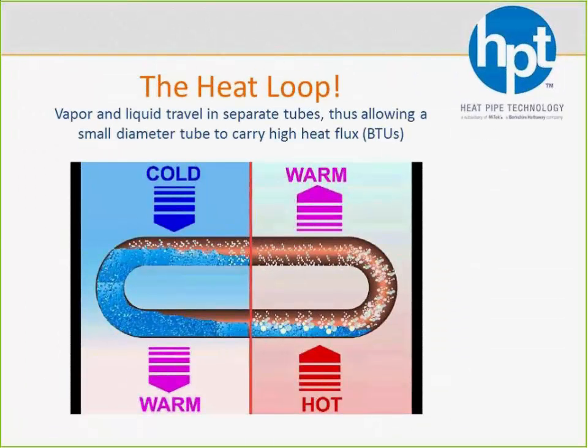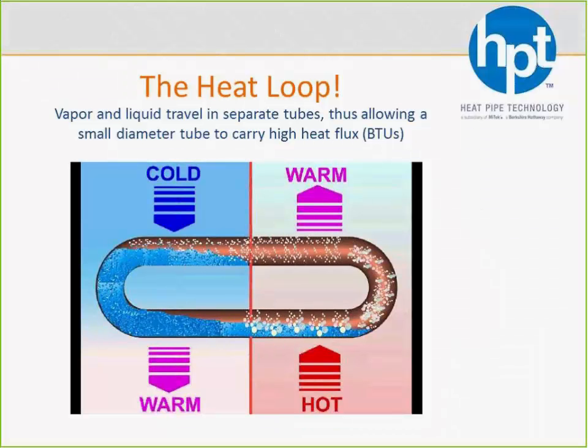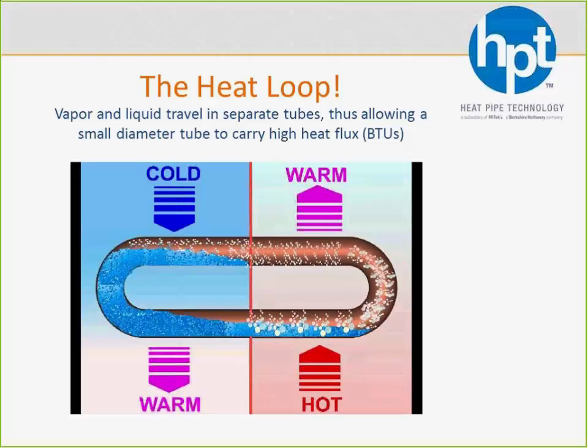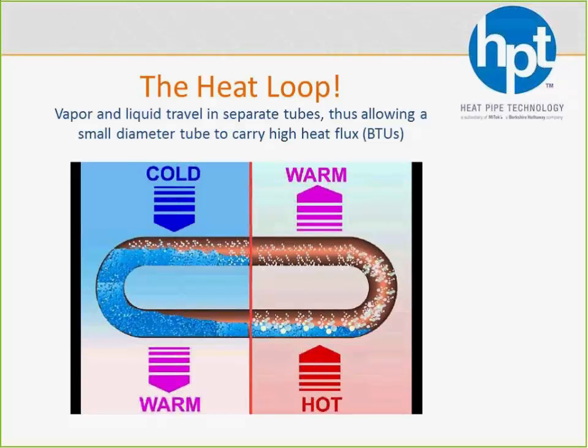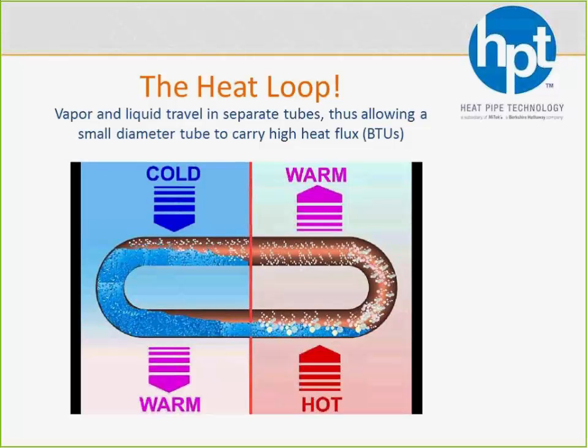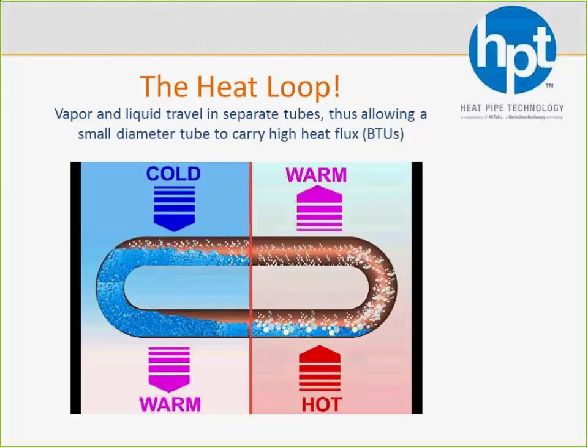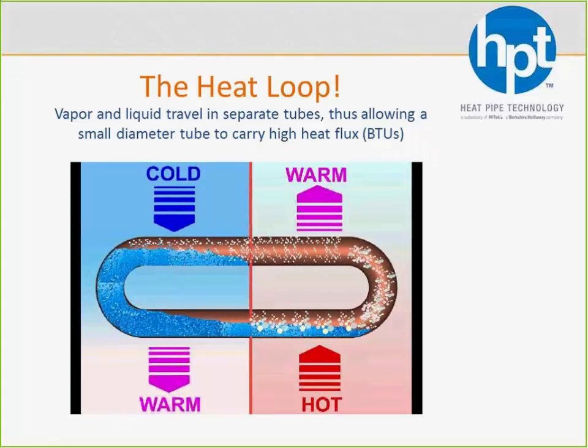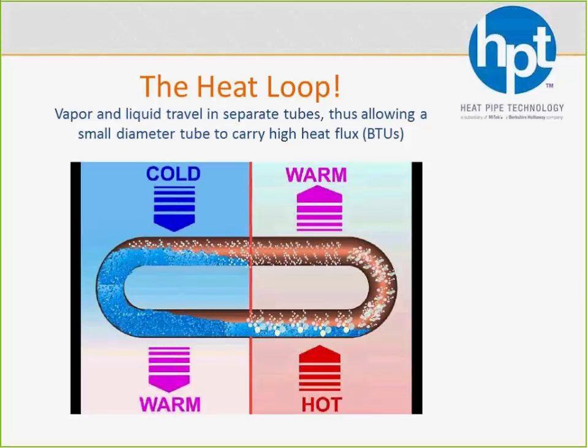We do it a little bit differently. We use what we call a loop circuit, where instead of a single tube with the heat going back and forth, we actually have what kind of looks like a racetrack, where you're going to have the liquid going one way, and let's say we're going from left to right here. The liquid's going to enter that hot air stream. It's going to pick up that heat and boil. It's actually going to go up the loop and then loop to the other side, where it contacts the cooler air stream, gives off the heat, condenses back to a liquid, goes down the loop, and it just keeps going in a racetrack type circuit.